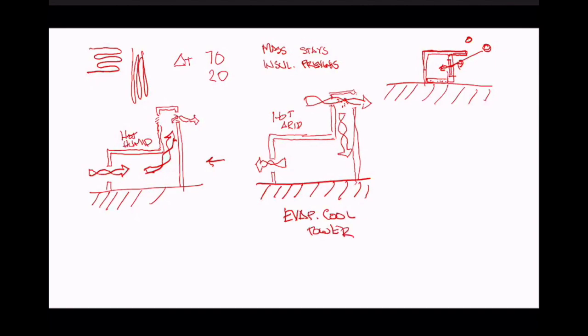People also get confused because the name is similar to a cooling tower. A cooling tower is part of our air conditioning system—in this case a chiller, something that makes chilled water. It doesn't have to be; it could be a refrigeration machine of any kind. But on one side, the hot side under high pressure, we can bathe that in water and pump it up to the roof or outside to a spot adjacent to the building or a central plant, with a nozzle letting that water fall into a pool. This is called a cooling tower.